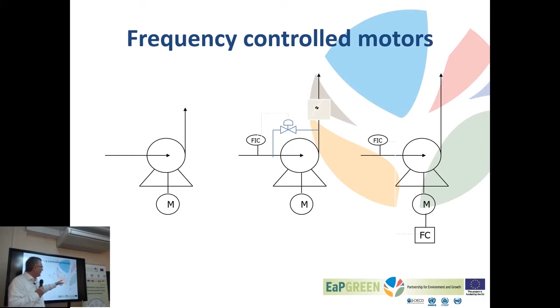The more efficient approach would be to use a frequency controlled drive to reduce or increase the rotations of my motor, thus the rotations of my pump, thus the flow. The impact of this is shown here in this slide. This slide compares the motor power over the range of delivery heads for conventional control versus frequency control for a certain pump. A freshwater pump, 60 kilowatts, which we analyzed years ago in a dairy. You see that these are the percentage of nominal delivery. Here is the motor power in kilowatts.